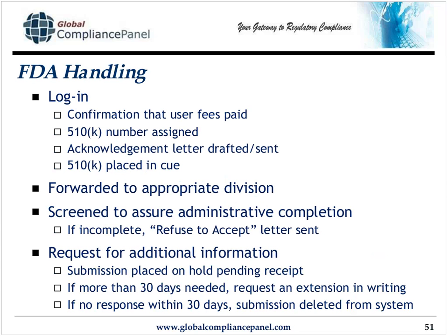They then forward it to the appropriate division based on the division that you've identified in your submission. And they're going to make sure that it's administratively complete, which is why if you have sections that are blank, bench clinical testing, for example, put a page that says clinical testing and then just write NA on it. And that way you avoid the possibility of failing the administrative review.